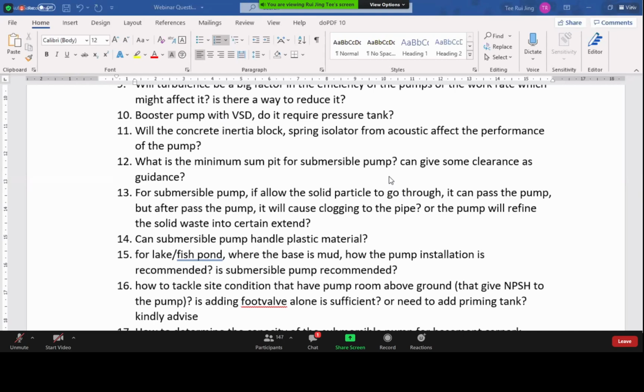Now, of course, the function of the pump is to drain off or de-water or clear off the water. So that means the water level will go to the bottom, right? That is where your pit sizing is important, to ensure that the water being cleared off does not exceed, let's say, around 3 to 4 minutes of the pump running, because then the motors will tend to get very, very hot because there's no water cooling the surrounding, and then it can overheat and damage the pump.